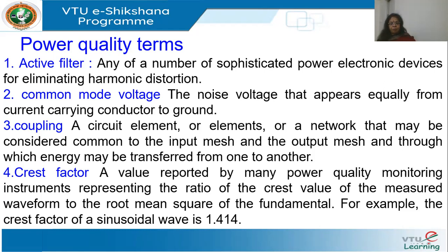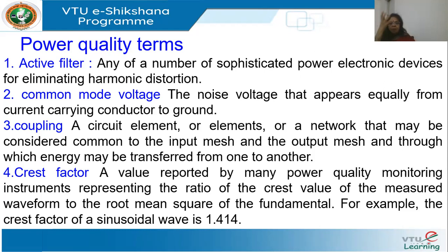Crest factor is the ratio of the peak value to the RMS value, as studied in basic electrical engineering. For a pure sinusoid, the crest factor is 1.414. The crest factor is important in the context of harmonics — it is a direct indication of how high the current or voltage can jump with respect to the average RMS value. Crest factor is therefore one important parameter in characterizing harmonics.